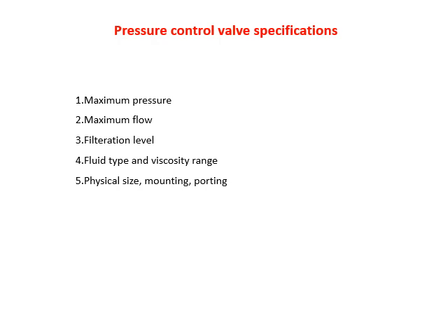If you want to purchase a pressure control valve for a particular application, then a few ratings or specifications you should know: what is the maximum pressure limit at which you are going to operate that valve, what is the maximum flow available at your end, what kind of filtration level you can achieve in that particular hydraulic circuit, what is the fluid type, what is the viscosity range of that fluid, and what is the physical size.